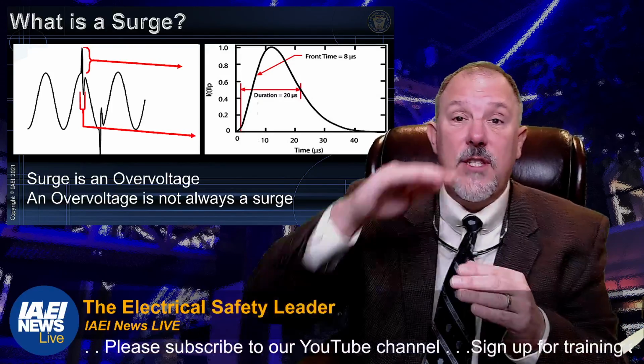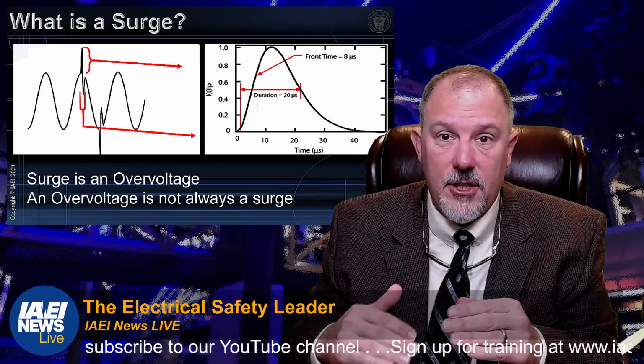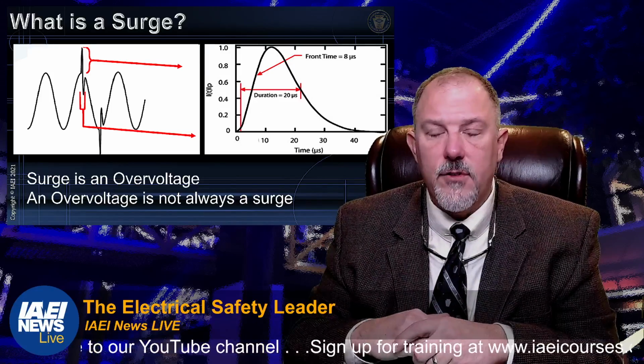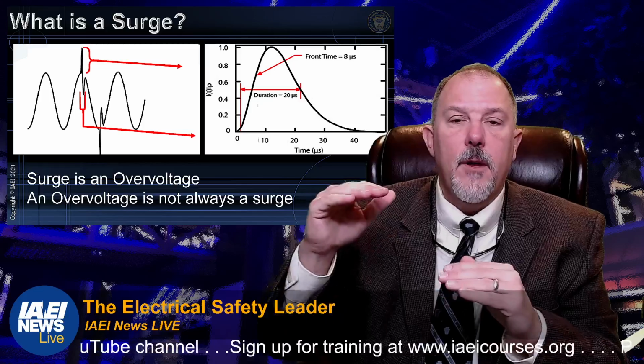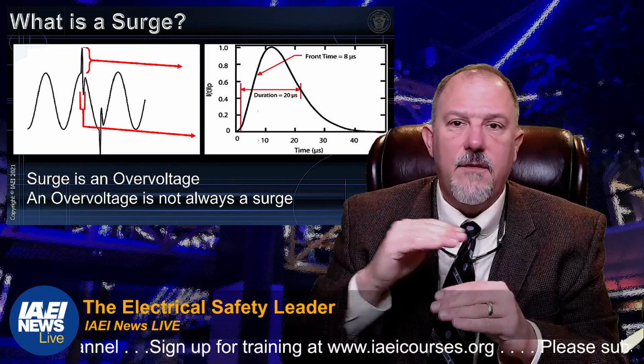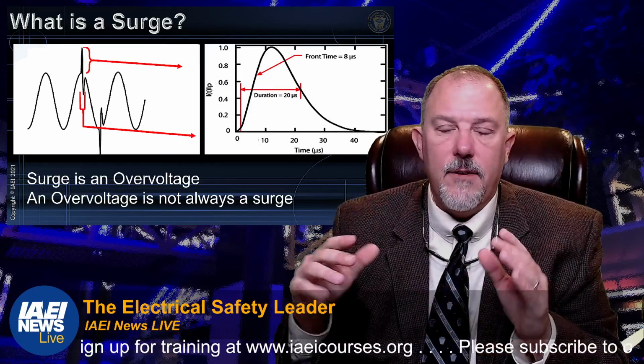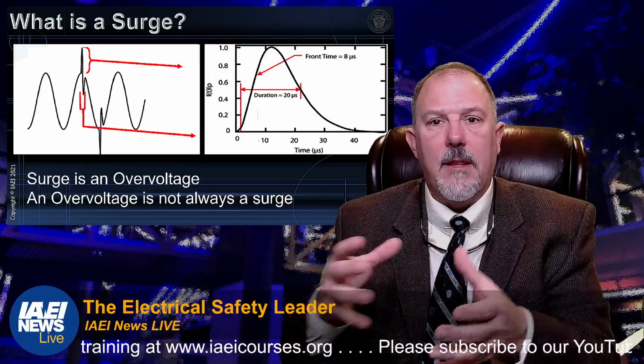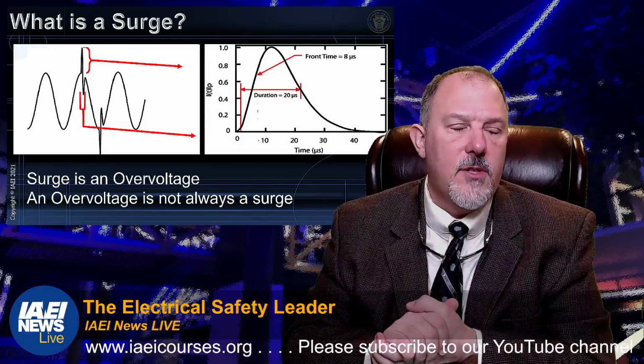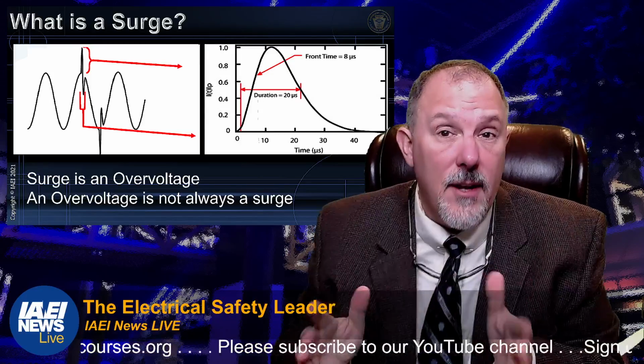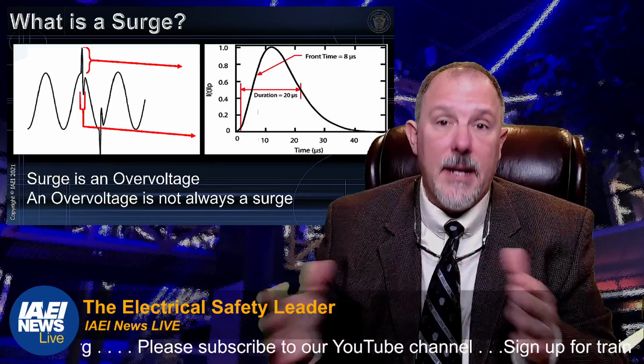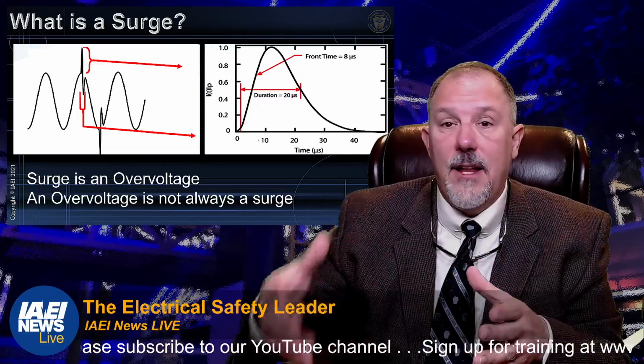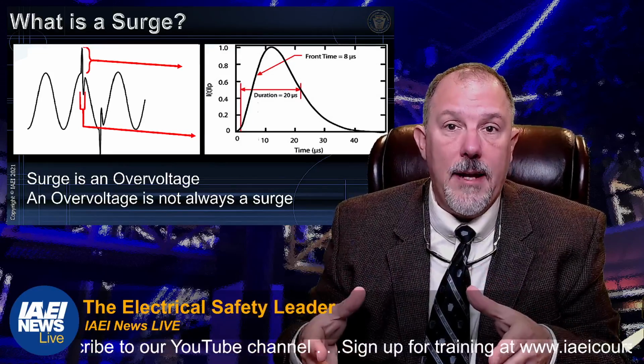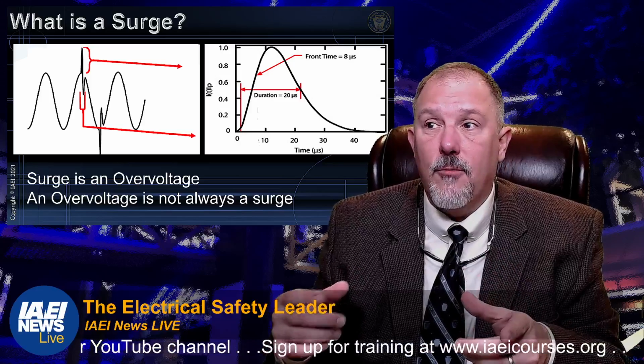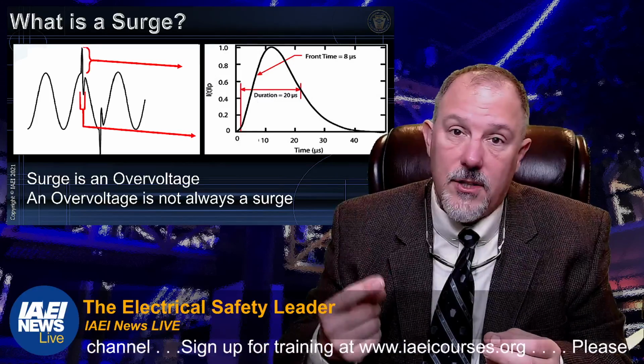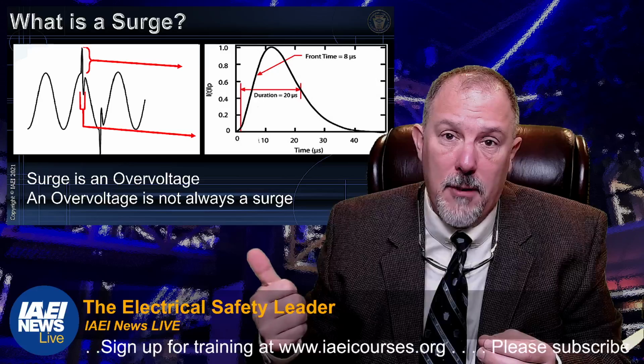which is why we'll tier the protection. And you might say, well, depending upon where you place the surge protective devices or transient voltage devices throughout the power distribution system, someone would say, well, that's overkill. Not necessarily. There are plans and approaches to provide a good level of protection for all equipment, and it rarely involves placing one surge protective device at the service equipment.